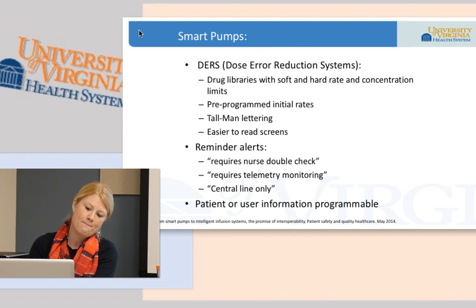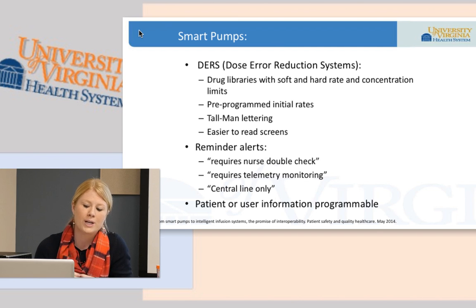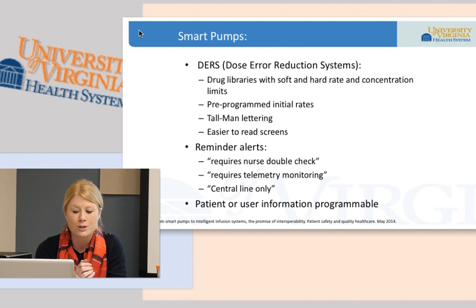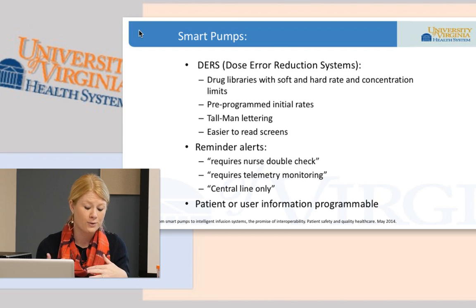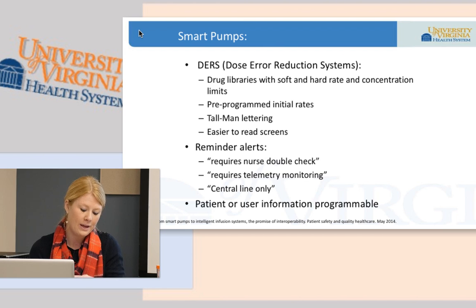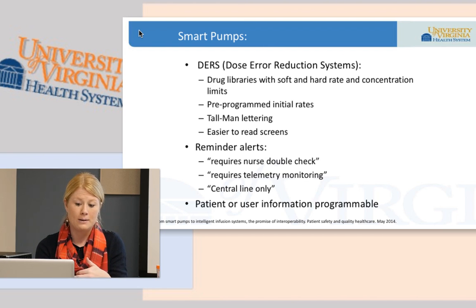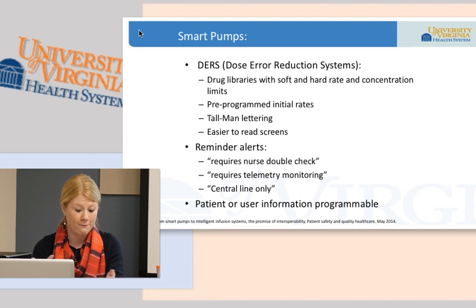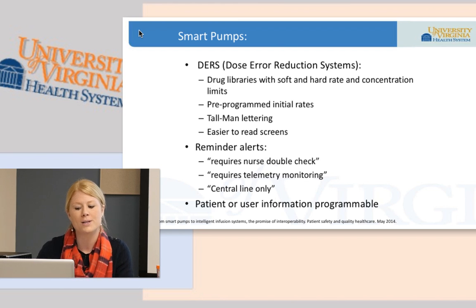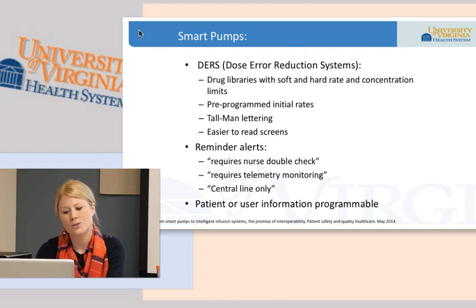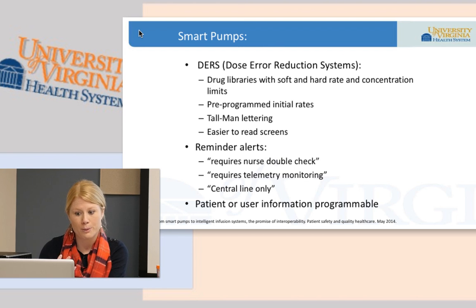So then we have the invention of the smart pumps, which really introduced the dose error reduction systems, or the DERS. So now we have the addition of drug libraries with soft and hard rate and concentration limits. So a soft limit is a suggested max rate or concentration that really questions the user if they are wanting to put the entry in because it's exceeded a limit that we feel is safe for the patient. However, it is overridable ultimately, but it just adds an additional safety feature of, is this really what you wanted to do? And then a hard rate limit or a concentration limit is the max and it's not overridable. We also had pre-programmed initial rates, the addition of tall man lettering, and an easier to read screen. So really that extra safety feature with the smart pump itself.